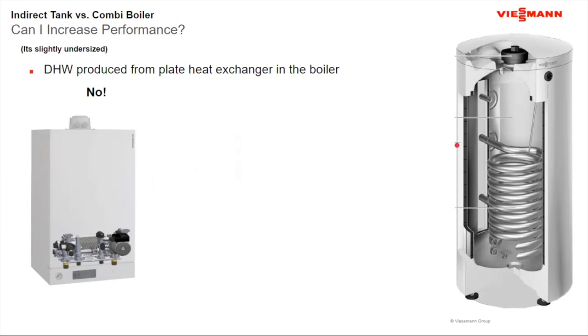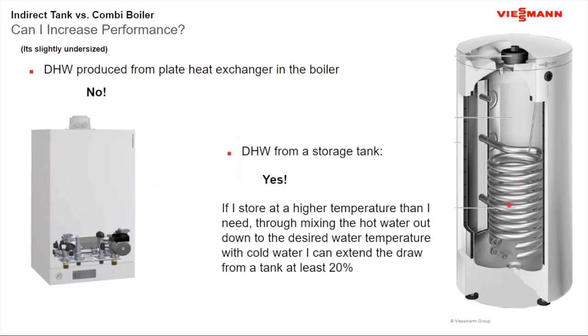But if I go to a tank style water heater, the answer is yes. So let's say I do a tank style water heater, and let's say I'm storing at 120 degrees Fahrenheit. And for whatever reason, they seem to run out of hot water a little bit earlier than they would like. And the question becomes, is there any way to squeeze out any more performance? The answer is absolutely. Let's not store at 120 degrees. Let's increase it to 140, maybe 145 degrees. And as the person pointed out in their question earlier, if I'm going to bring this up to 140 to 145 degrees, please install an ASSE 1070 rated, maybe no, 1017 rated mixing valve, a point of use, point of storage mixing valve to ensure nobody in the building gets scalded.